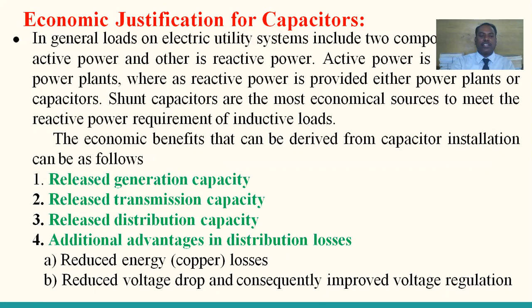Additional advantages in distribution losses, such as reduced energy copper losses. This is one of the benefits of capacitors installed in the system. Reduced voltage drop and consequently improved voltage regulation, and released capacity of feeder and associated operators. That means a feeder releases its maximum capacity. And similarly, postponement or elimination of capital expenditure due to improvements and expansions.